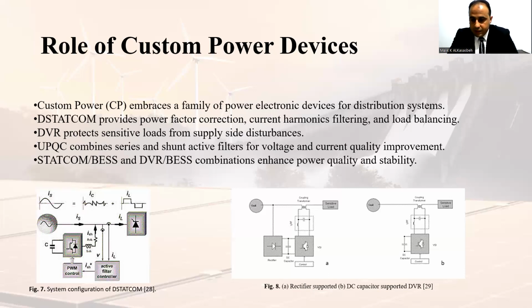As shown in figure number 7, we can see the sources, and the pulse width modulation controller connected with the active filter controller, and also the supercapacitor and inverter, in the STATCOM configuration. In figure number 8, we can see the rectifier supported, DC capacitor supported dynamic voltage restorer. This is the load, and this is the grid, connected together, and the same thing in figure number B.